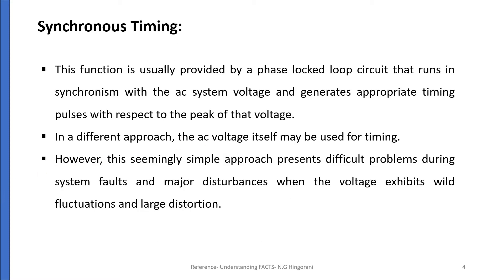Synchronous timing is usually provided by a phase-locked loop, or PLL circuit, that runs in synchronism with the AC system voltage and generates appropriate timing pulses with respect to the peak of that voltage. In a different approach, the AC voltage itself may be used for timing, but it presents difficult problems during system faults and major disturbances when the voltage exhibits wild fluctuations and large distortions. Hence, we need a PLL block to give us the exact instant at which the voltage peak is achieved.